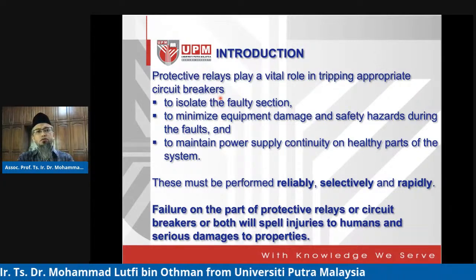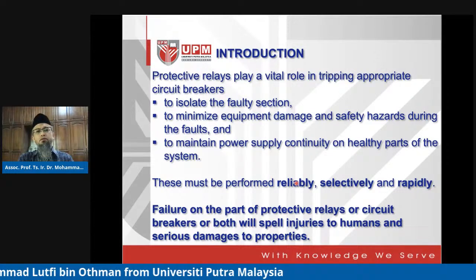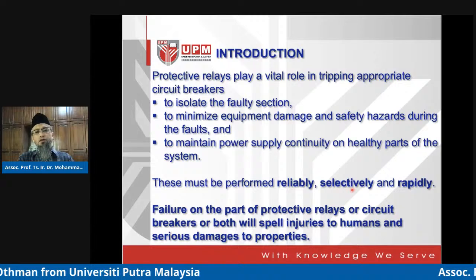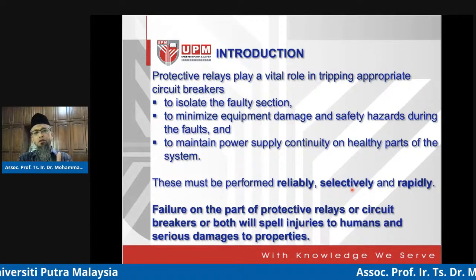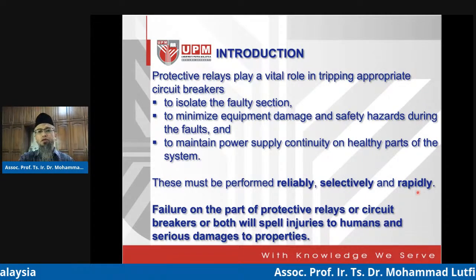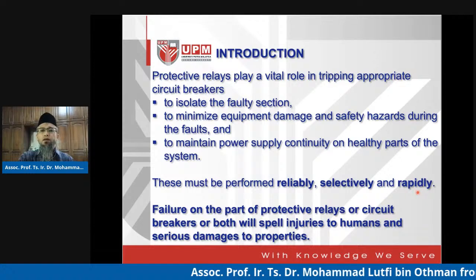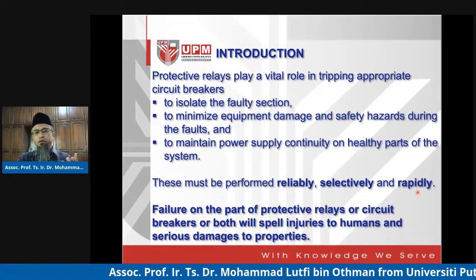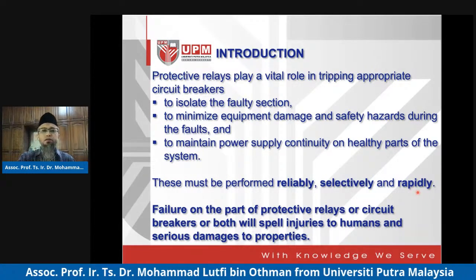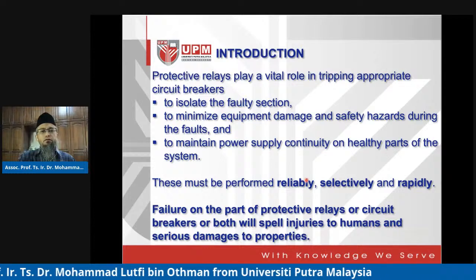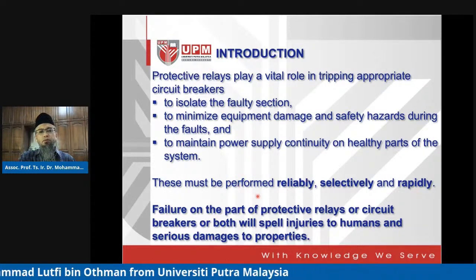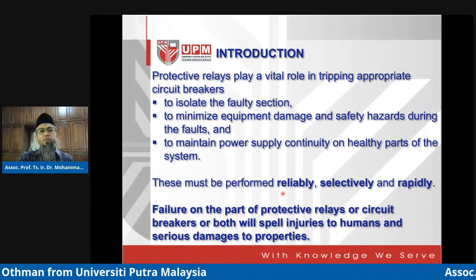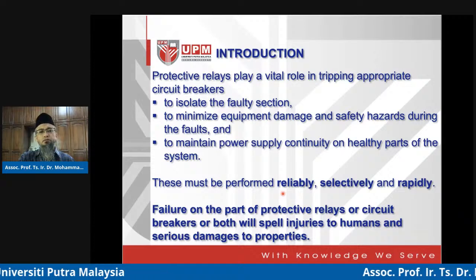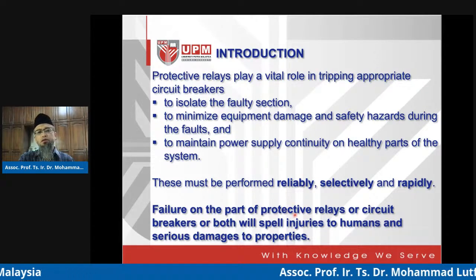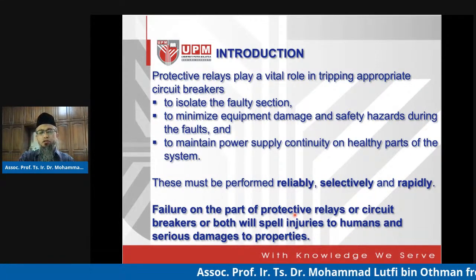The relays must operate in a reliable manner, selectively, meaning it only operates where it is actually expected to operate, and rapidly, meaning it has to operate in compliance with the required time frame. So why is it really important? Because failure on the part of protective relays would be disastrous. It would spell injuries to humans and damage to properties.